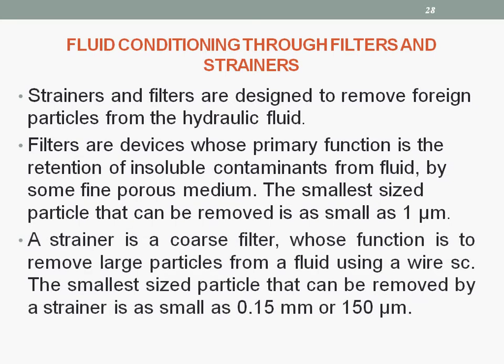The filters are used to retain the insoluble contaminants from the fluid with the help of a porous medium, and the smallest particle which can be removed is as small as 1 micron in the case of filters. Similarly, strainers are used as a coarse filter, whose function is to remove the larger particles. Coarse means the larger particles, and the smallest particle that can be removed with a strainer is 150 microns or 0.15 mm.